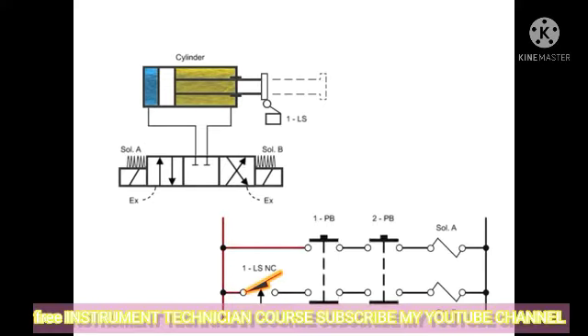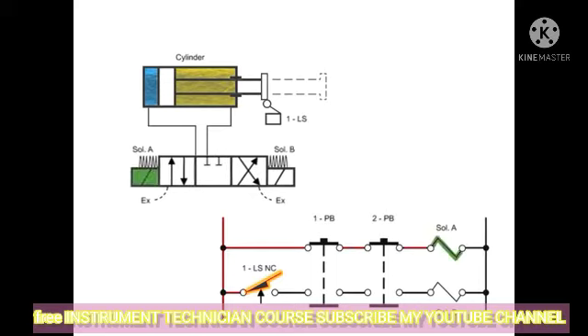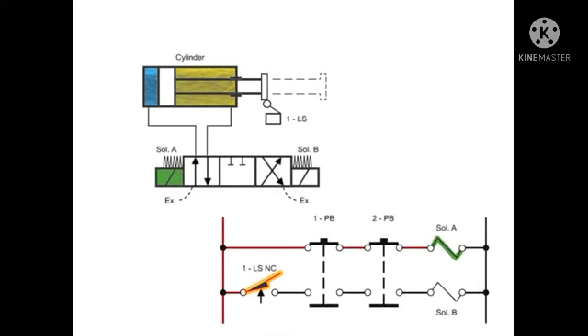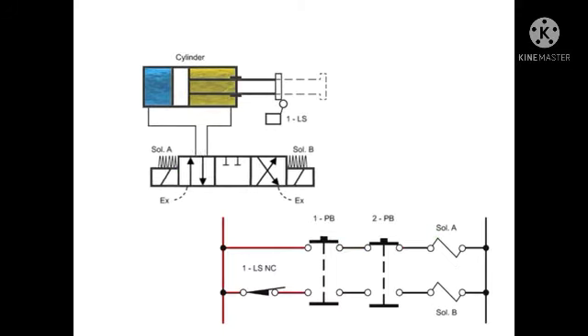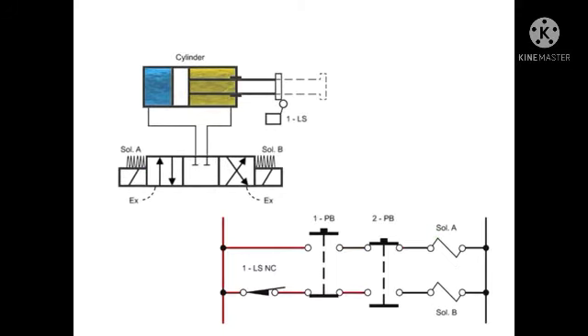Both buttons must be pressed to energize valve solenoid A and start the cylinder forward. When the cylinder begins to move forward, limit switch one is released and goes to its normally closed position. If either button is released, both solenoids de-energize and the springs return the valve to its neutral center position, stopping the movement of the cylinder.